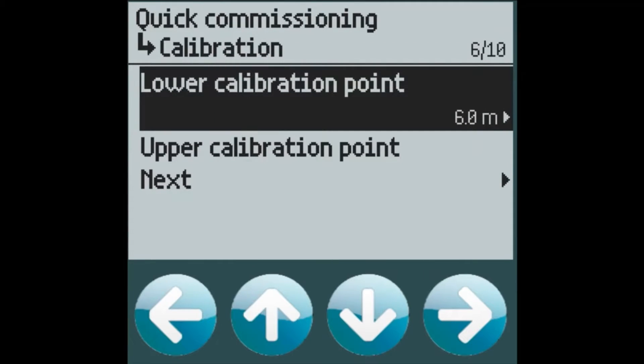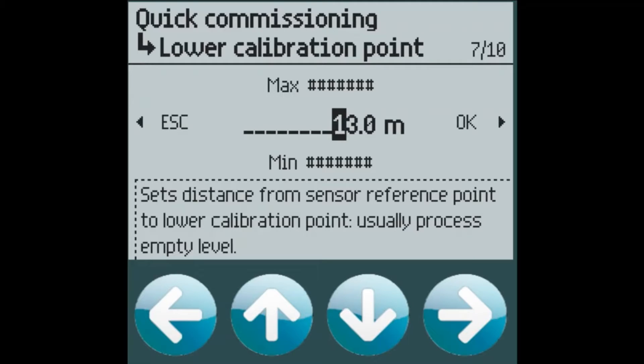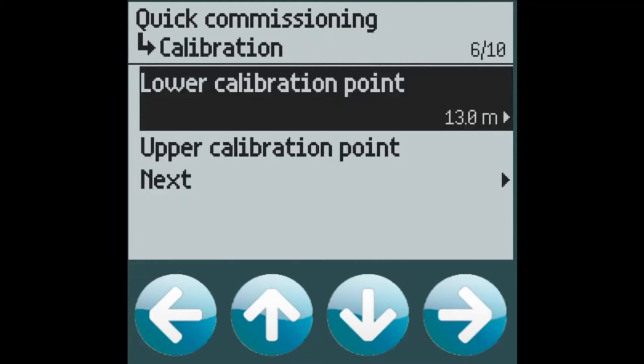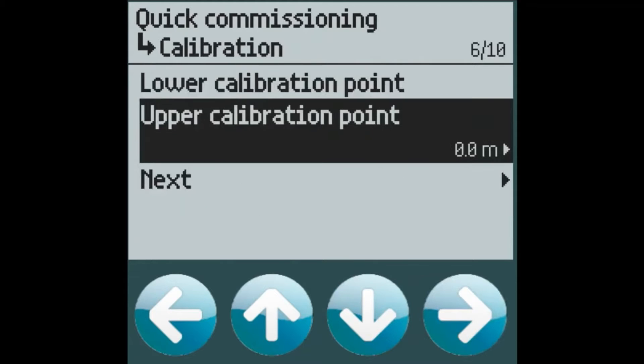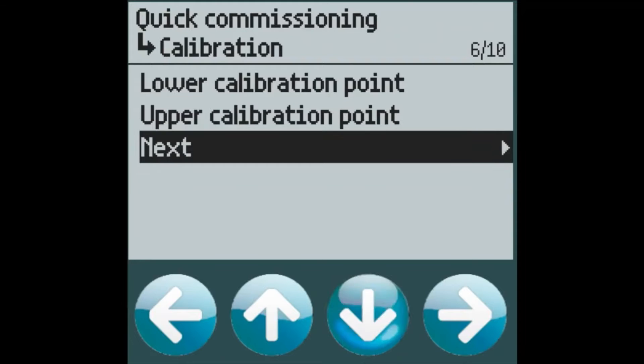The lower calibration point is the distance from the sensor to the bottom of the tank. In this case in our application this is 13 meters. The upper calibration point is the distance from the full material level to the sensor, in this case 0 meters because we can measure directly up to the sensor face on the LR120.